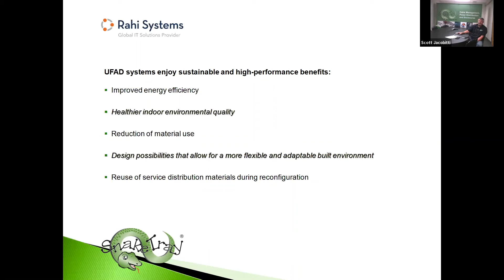How does that really work into existing buildings? Retrofitting an existing slab building to a raised floor is very minimal at best—there's not a lot of that going on. We do have some cell floors out there, very shallow floors, that allow us to do that, but those aren't used for any type of air management, just basically cable management. Where we're going to see the most forward movement on a raised floor is in new construction, where the architects and owners get together.